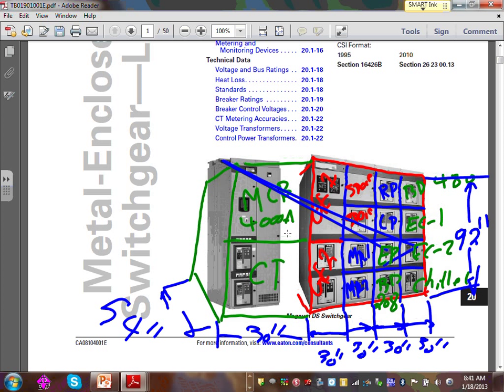So what are the small buckets again? They are circuit breakers. So these two are assigned for one circuit breaker for generator one. These two are assigned for one circuit breaker for generator two. And the rest of them, each pocket, is for mechanical panel 1, 2, receptacle panel, lighting panel, emergency panel, bus duct 208, bus duct 480, environmental chamber 1 and 2, and chiller.